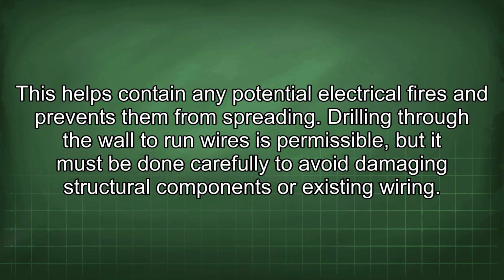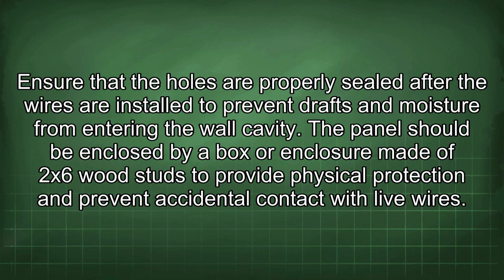Drilling through the wall to run wires is permissible, but it must be done carefully to avoid damaging structural components or existing wiring. Ensure that the holes are properly sealed after the wires are installed to prevent drafts and moisture from entering the wall cavity. The panel should be enclosed by a box or enclosure made of 2x6 wood studs to provide physical protection and prevent accidental contact with live wires.